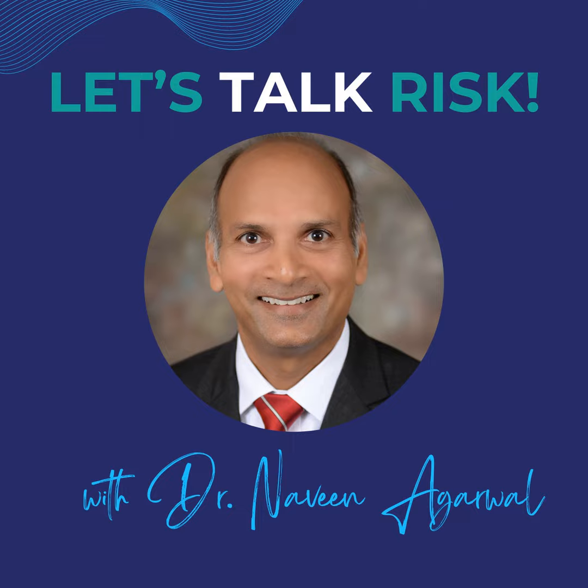As highlighted by a comment, in this case, from a 13485 perspective, the first mistake is not paying attention to the second sentence of Clause 7.3.3, where it requires that design inputs, that is requirements, be reviewed for adequacy and then goes on to specifically require that they are able to be verified and validated.